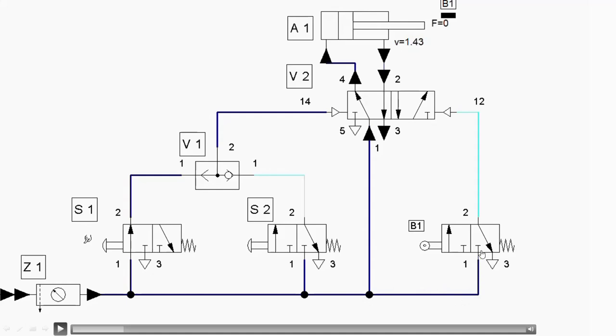This is the blocked position so air will not enter there. It has to go through this particular opening and port. Ports 1 and 4 are now connected, so air will flow from the compressor through the FRL unit to port 1, from port 1 to port 4, causing the forward stroke. The air from the rod side will go through ports 2 to 3 to the exhaust. This is our forward stroke giving a positive velocity.